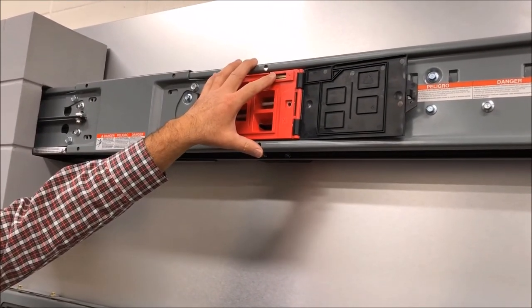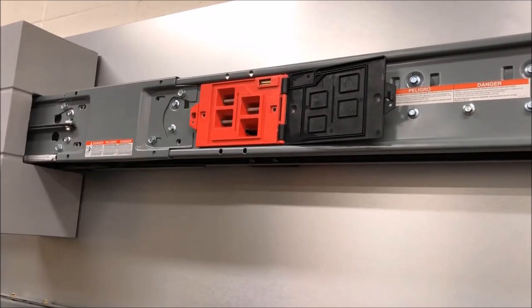3 and 4-pole plug-in units are interchangeable except on 800 amps and above. When installing a 4-pole plug-in unit in a 3-phase, 3-wire busway, there will not be a neutral connection.